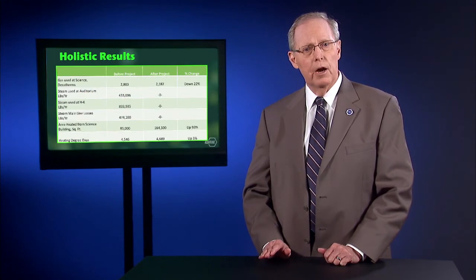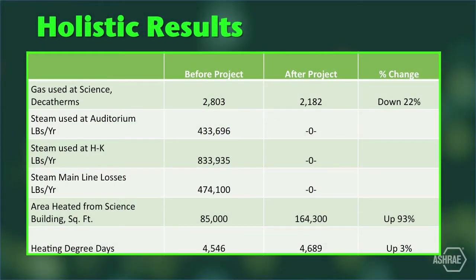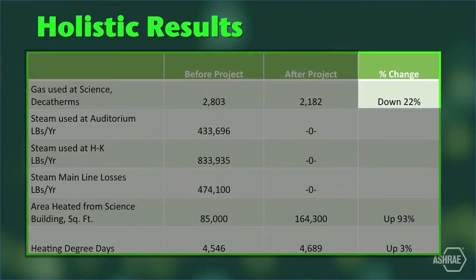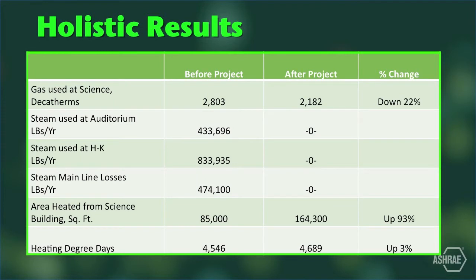Three buildings are now heated from the Science Center, which is double the area, and the amount of gas used actually went down 22%. We converted two buildings from steam to low-temperature hot water and decommissioned 1,000 feet of steam mains, eliminating about 1.8 million pounds of steam per year.